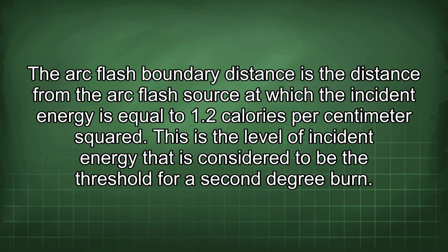The arc flash boundary distance is the distance from the arc flash source at which the incident energy is equal to 1.2 calories per centimeter squared. This is the level of incident energy that is considered to be the threshold for a second-degree burn.